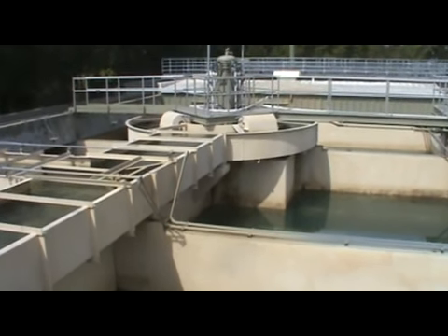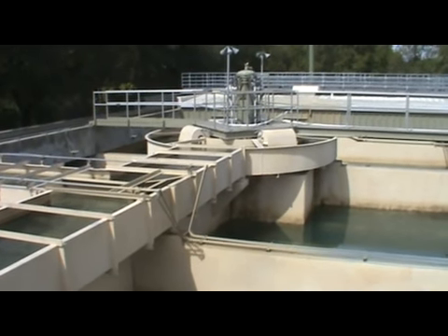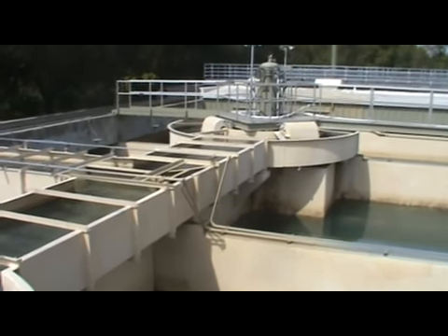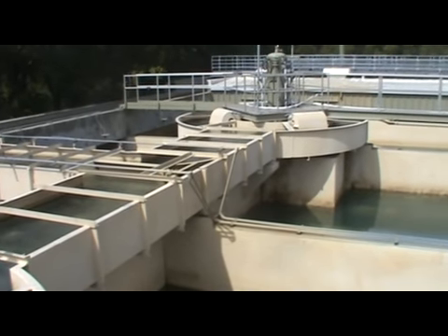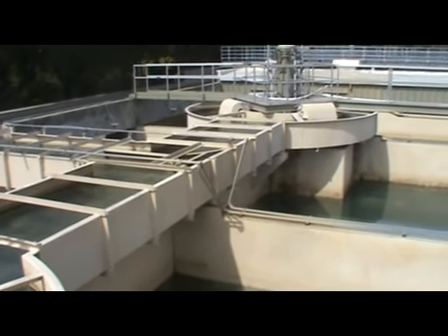So we add positively charged ions to the water in the form of coagulants. In this case, we're using alum, and they bang together and start to collect those negative ions and form that floc. So what happens is those negative ions that are still left come down here and hit the filter bed, and they get buried into the filter bed as the water is pushing through. They get filtered out and bury themselves into the filter bed at separate levels. And as any other negative particles come along, they catch them and hang on to them.